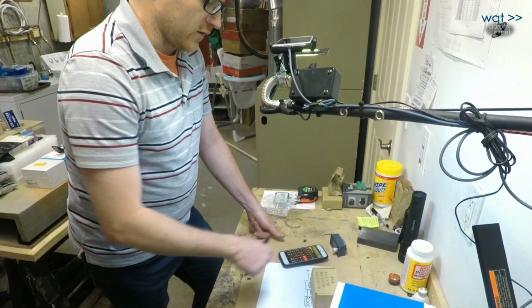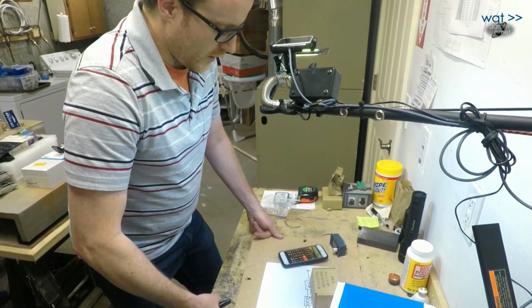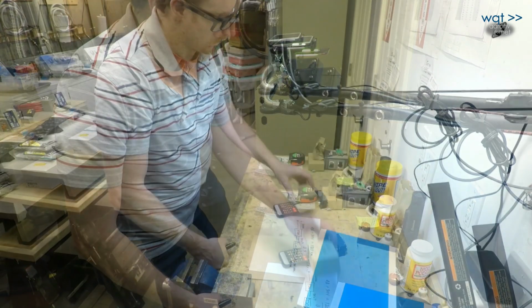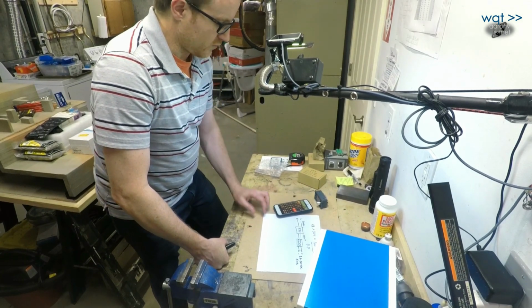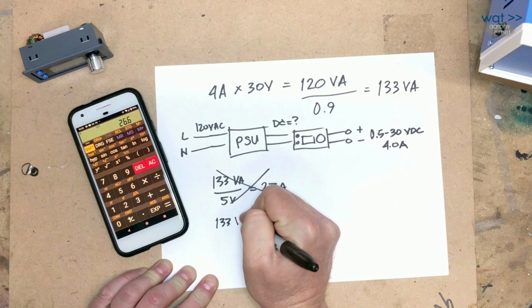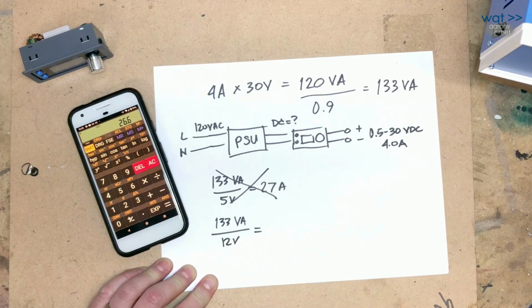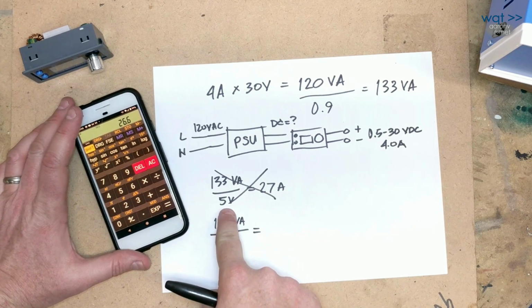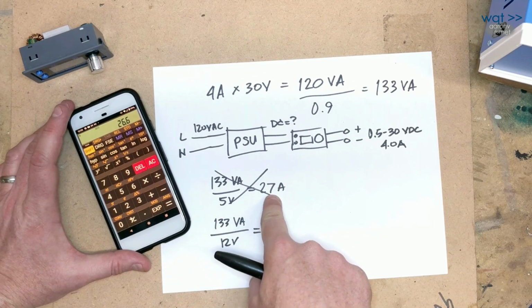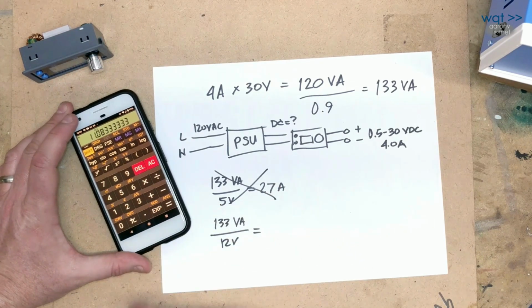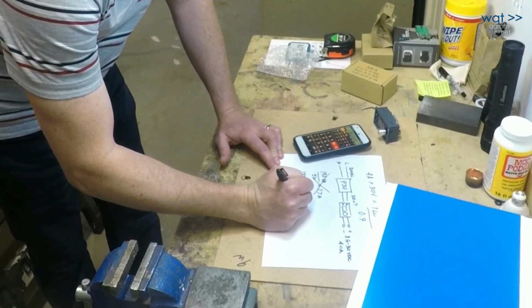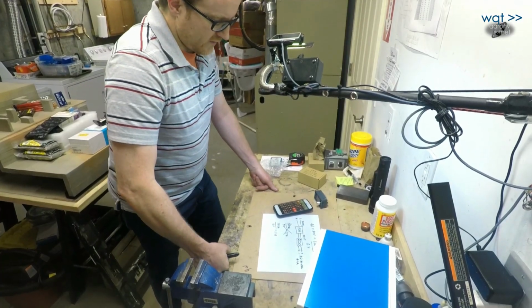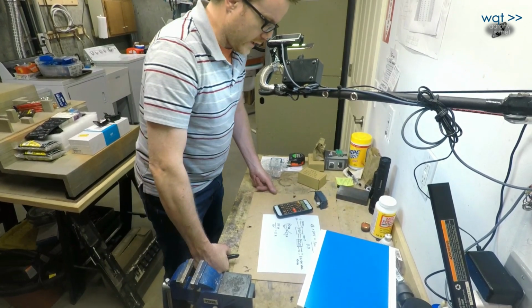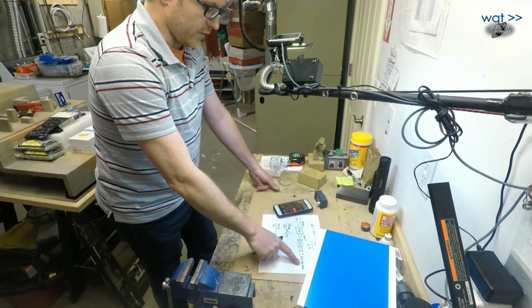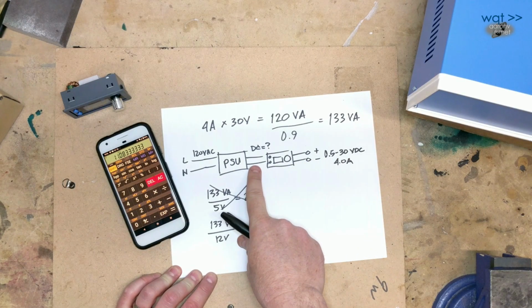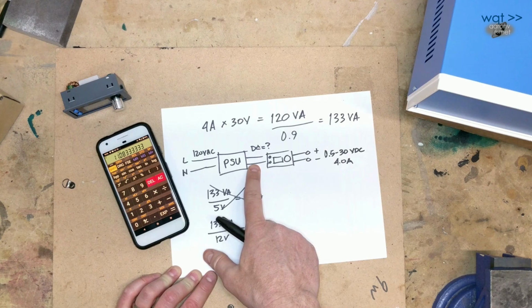I can now input as little as 5 volts here, but if I really want to input 133 VA, that's just not practical. So my next common supply size is 12 volts. 133 VA divided by 12 volts - well, 12 is a little bit more than twice 5, so I'm going to expect that to be a little bit less than half of 27, but let's get the exact number: 11 amps, more or less. That's a little bit more approachable, but it's still a bit much. And what you're seeing here is that if I want the maximum output of 30 volts, I should probably be putting in a DC voltage that's a little bit closer to the 30 volts I want.